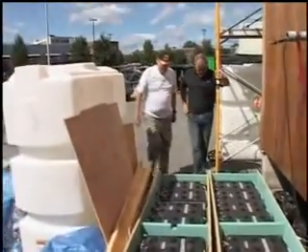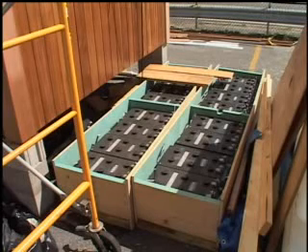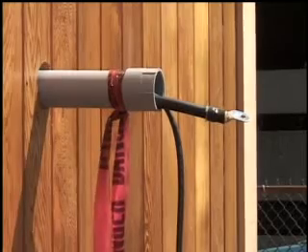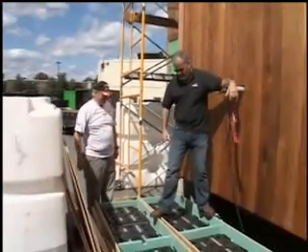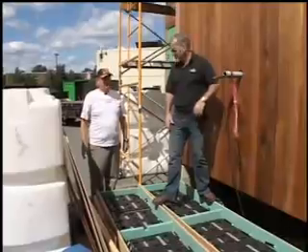So these are the battery boxes and there are three of these — one we're building up on the other side and these two. Each of these boxes holds four of what's called an 8D battery. These are some of the biggest batteries made and each battery is 12 volts. They're lined up in groups of four because we store energy at 48 volts. They're going to sit about 15 inches off the wall. They're not weatherproof on their own, but when they're stacked up it's all enclosed. I'm really excited to see this when the project's completely done and the house is all lit up.